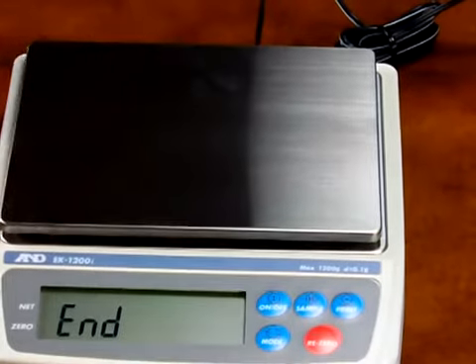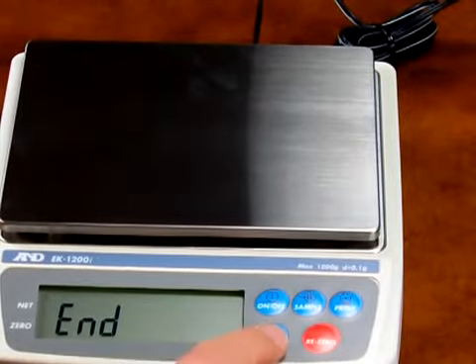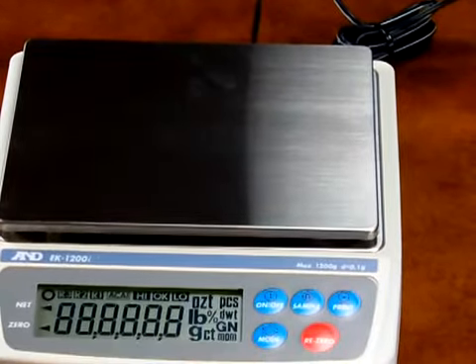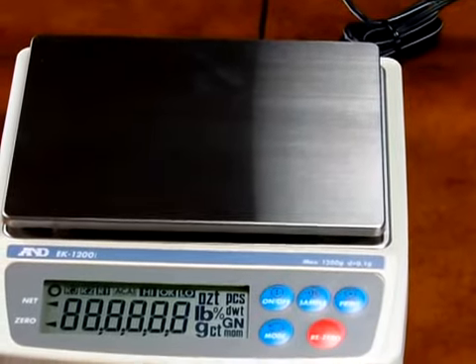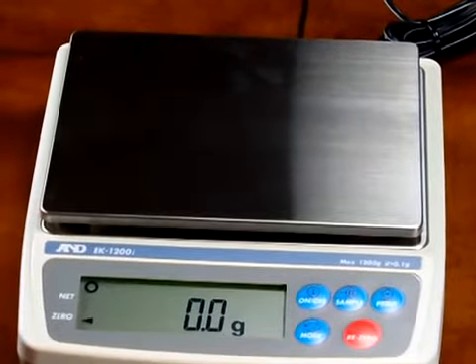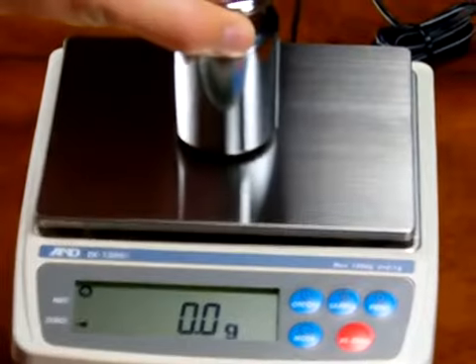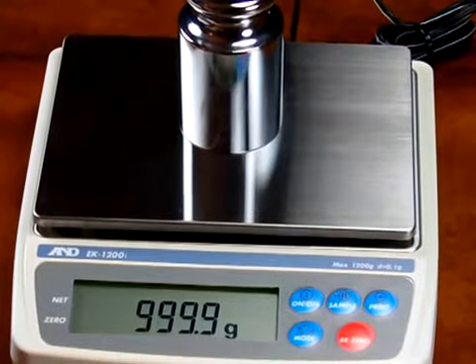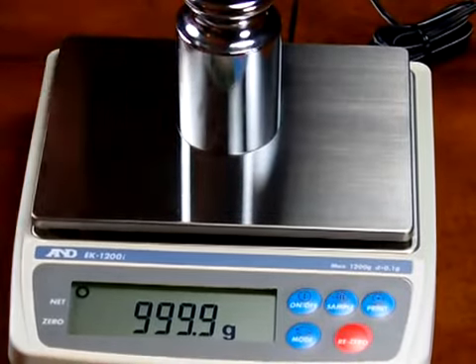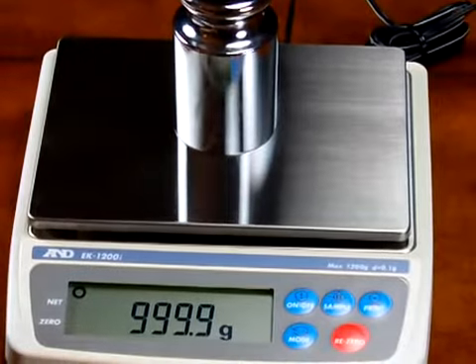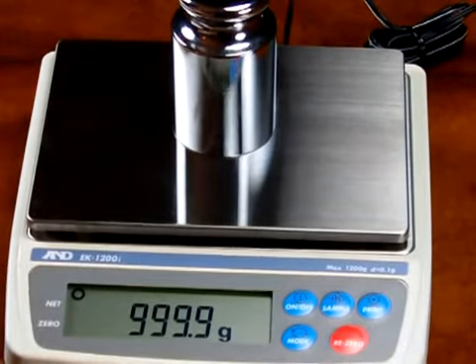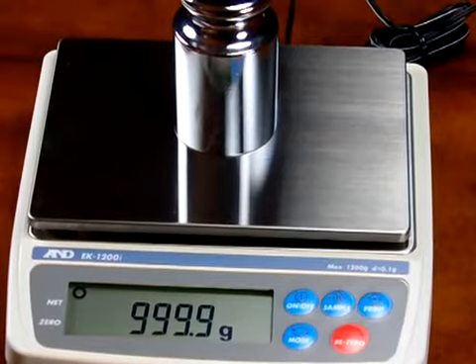We'll remove the calibration weight, press the mode button. This will reset the balance. Balance powers up, and the scale is now calibrated. So again, this is 1200 grams by 1/10, so it can be off by 0.1 gram.